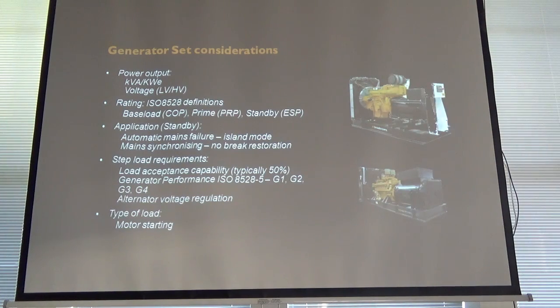Okay, so are these all high-speed diesels? 1500 RPM units, all of them. Yes, they tend to be the only ones that we supply now for these type of applications. So again, the sets are very reliable. So if, for instance, you had a start signal on a unit, assuming it starts first crank, it can be up to 90% of rated voltage and frequency within 8 to 10 seconds.